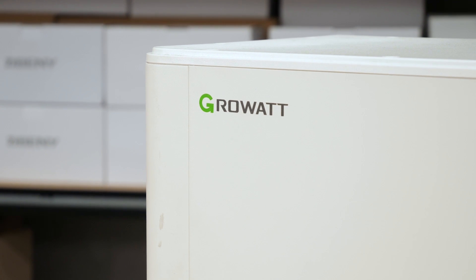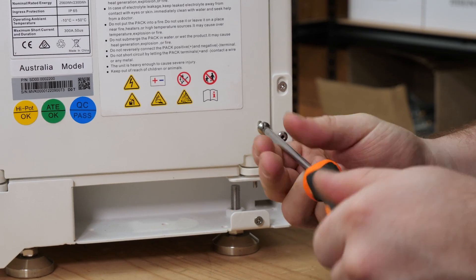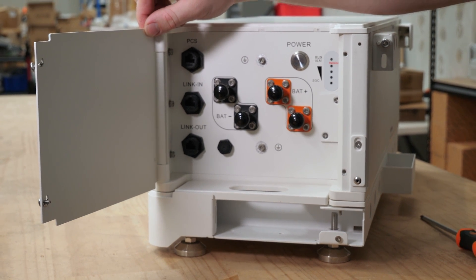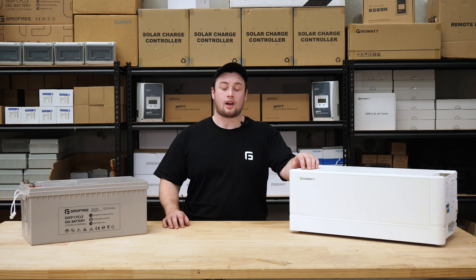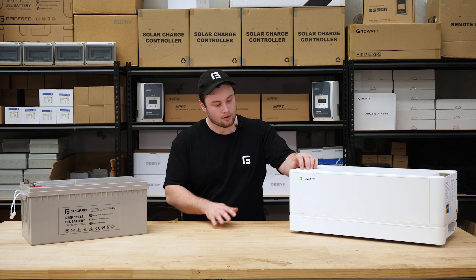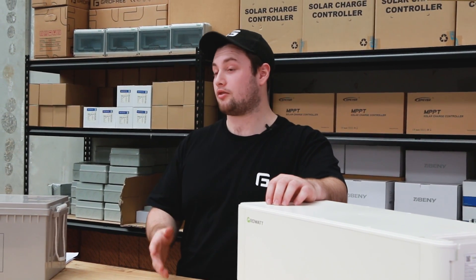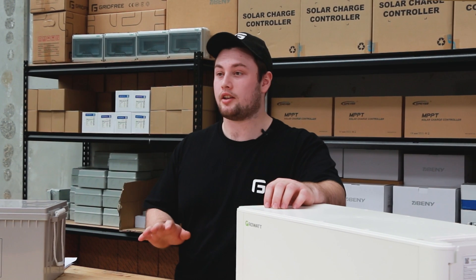We recommend these for larger systems or systems you're going to be living on full time. The cells inside the lithium unit are lithium iron phosphate — they're cobalt free and one of the safest lithium technologies out there. It's all protected by a BMS, or battery management system. Our lithium batteries are specifically designed to interface with our Growatt hybrid inverters, meaning the inverter is going to charge it correctly and ensure the banks are balanced. All of this is housed in a robust enclosure designed specifically for modularity and easy expansion.